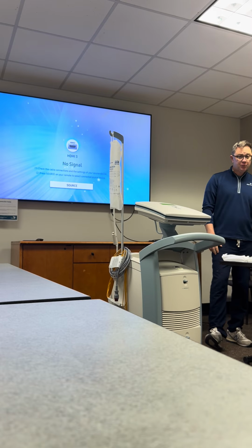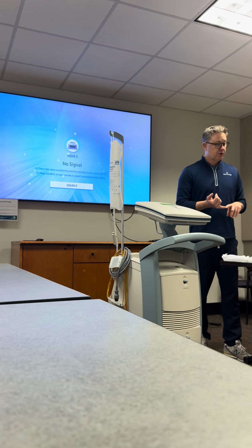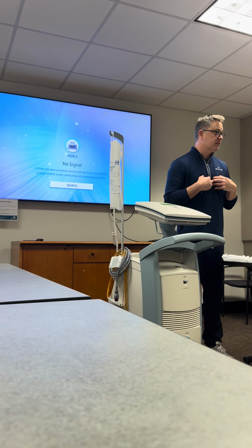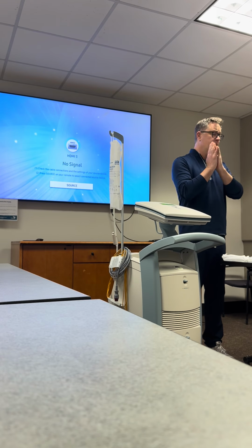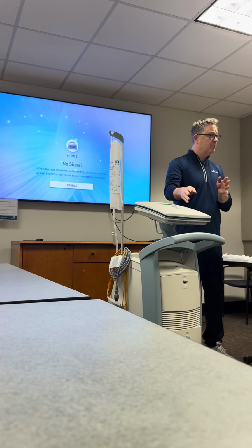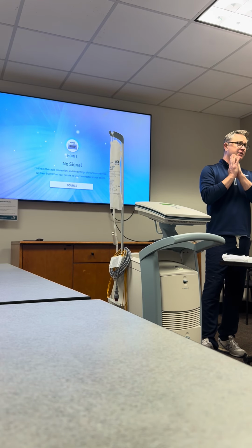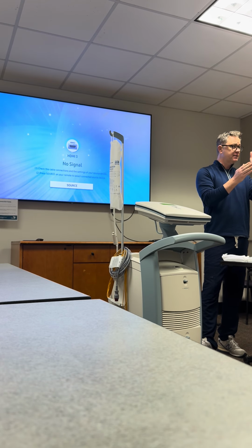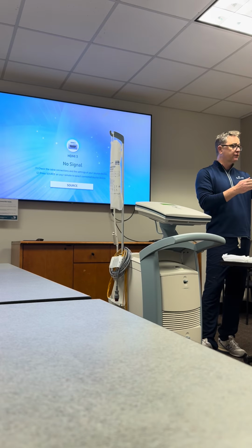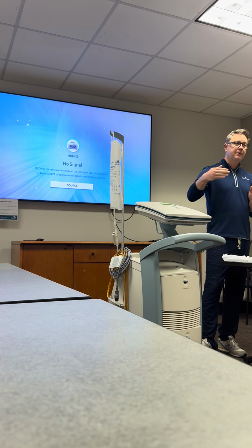That being said, there's two primary triggers. So first trigger is going to be your ECG if we're able to get leads on the patient. Balloon pump, when you hit start, puts it in the auto mode, and in the auto mode, it's going to look for that ECG. It's going to set up its timing based on those R waves.